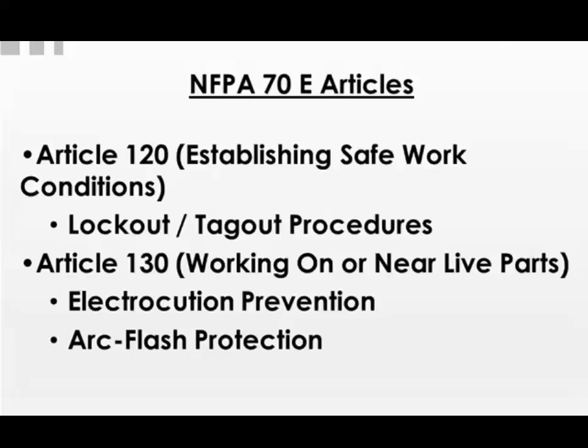But if somebody has to troubleshoot, or the example I give, this is kind of an extreme example, but it makes the case. If you've got somebody in a hospital and they're on life support equipment, obviously, and there's some kind of fault or trouble with it, somebody's not going to be able to de-energize that, right, for obvious reasons. They're going to have to work on it live. Well, there are very specific requirements under NFPA 70E. Article 130 talks about working on or near live parts. It's designed to prevent electrocution and to provide arc flash protection.